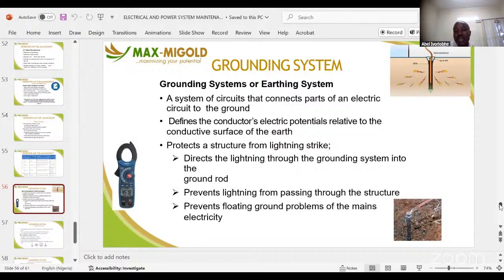Like on the island here, your rate of maintaining earthing might be low because we are in a swampy, waterlogged environment, and it's salty. So the materials that you require to maintain your earth arrangement are salt, that's an electrolyte, sodium chloride or ammonium chloride, depending on what is recommended.